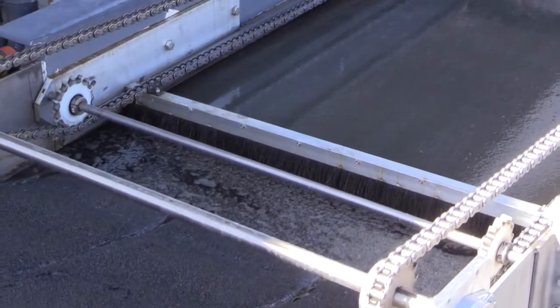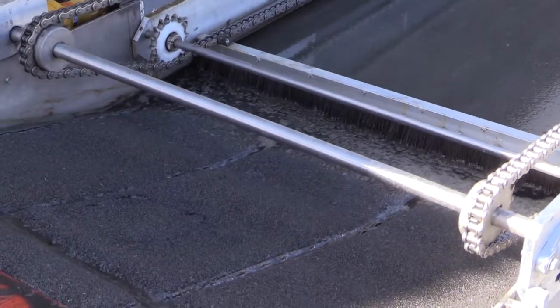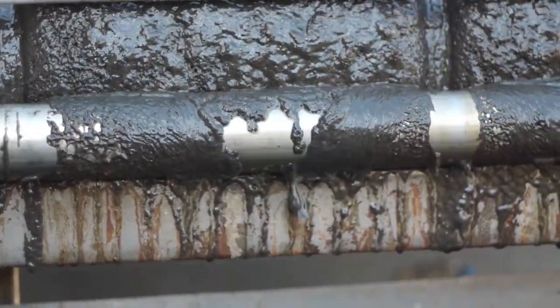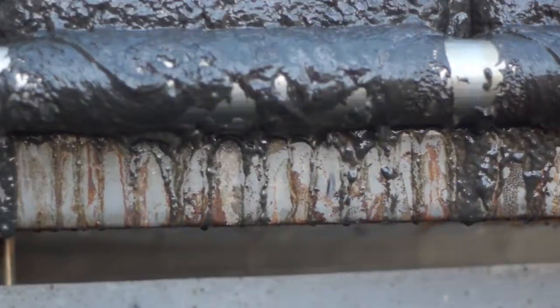Then our mechanical process — our rake — pushes it across the surface of the water and onto our oleophilic belt, which pulls that oil in off the surface. Then the oil belt rolls off, and you have an additional roller which acts as a doctor blade, and the oil and the sludge go into the hopper.